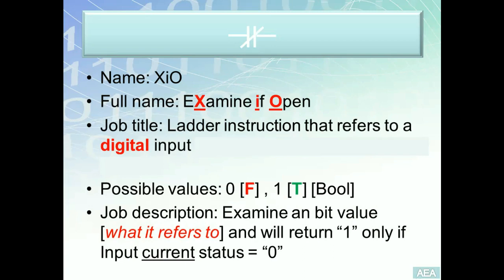Similar to XIC, the XIO will be tied to a discrete input through an address and will keep monitoring and examining that input. If that input is open, it will be reading zero in the PLC memory. That's when the XIO, wherever it exists in the program, will be true and will show the green bar on both sides of the instruction. If it was examining a closed state input, it will be false wherever it exists in the program.